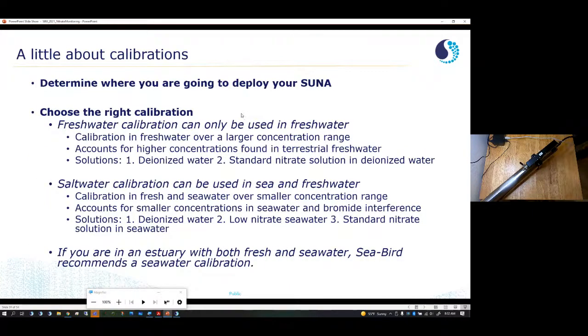One thing about the calibration, the first thing you're going to have to do is determine where you're going to deploy your SUNA. The really nice thing about the SUNA is that it can be used in multiple environments, but those environments have very different optical characteristics, and we have to calibrate it differently as a result. So you really want to choose the right calibration. If you're using it in a freshwater application, typically anything terrestrial, lakes, streams, whatever, you're going to want to use a freshwater calibration. The reason is that nitrate concentrations are typically a lot larger, so we calibrate over a larger concentration range. And there aren't as many interfering species, for CDOM or for dirty, muddy water, any material in the water, but we don't have bromide interference, which is what happens in seawater. So for that calibration, there are two solutions.